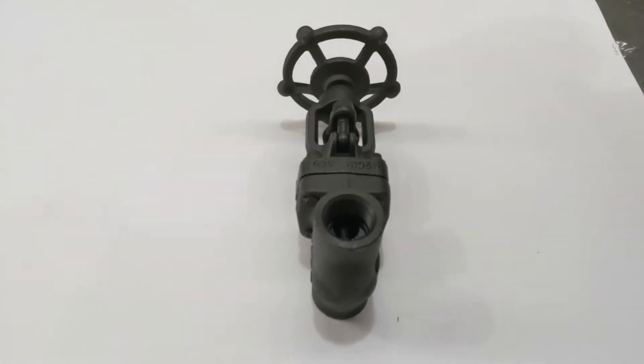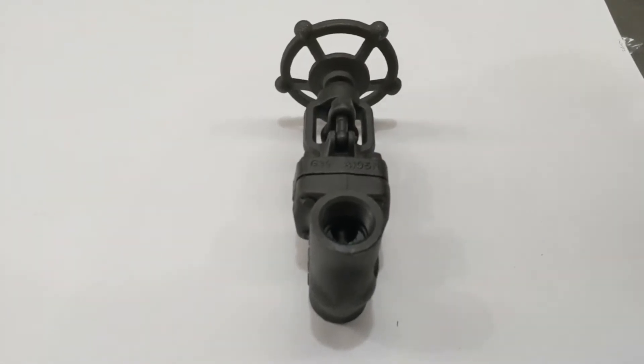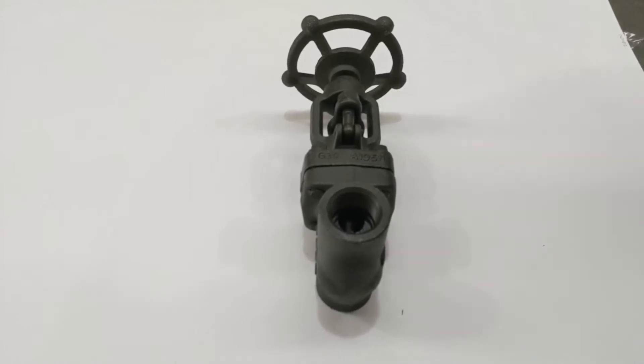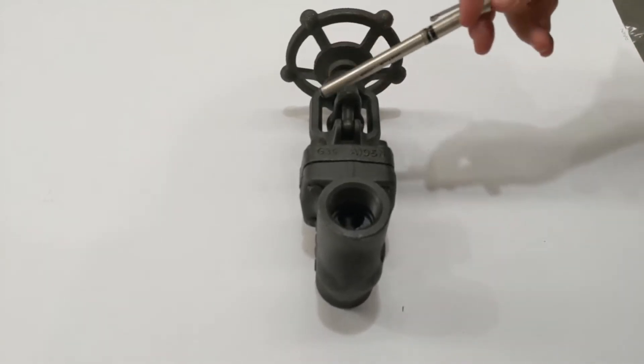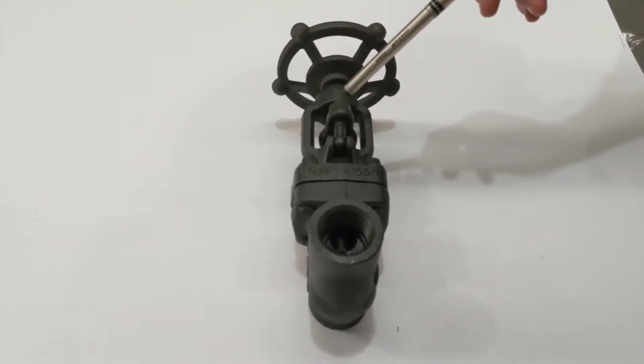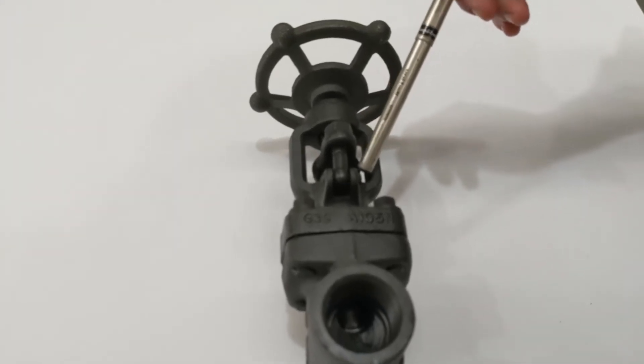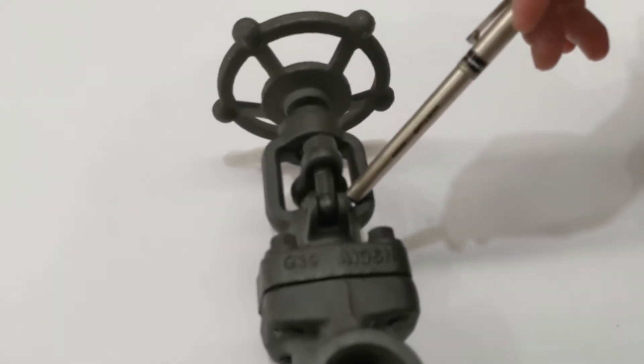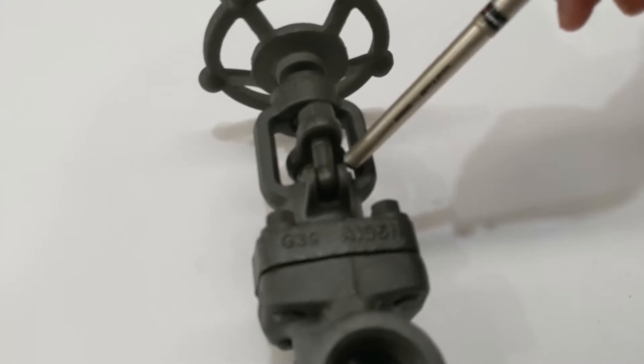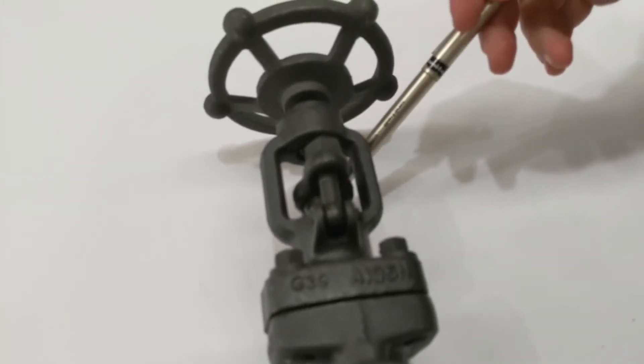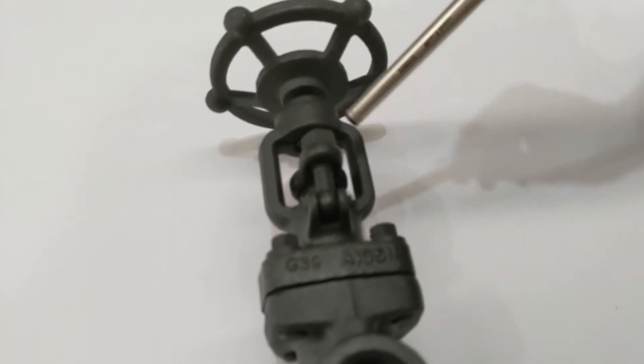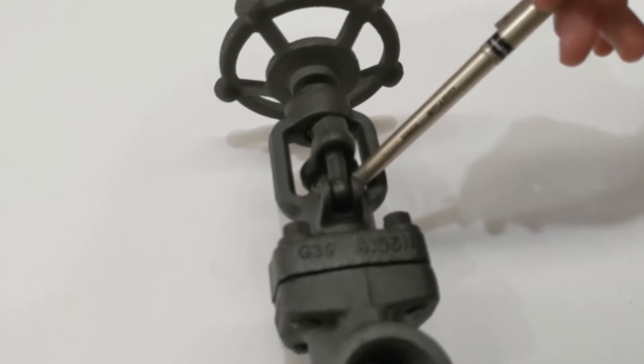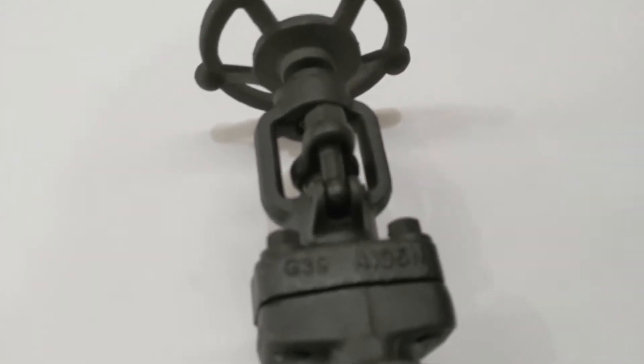This is our A105 forged steel class 800 globe valve. It's got an outside stem and yoke which you can see around here. This retains a gland seal just in here, so if this seal ever wears over time and you get seepage, you can tighten these two nuts down here to put more pressure back on the gland to seal it.